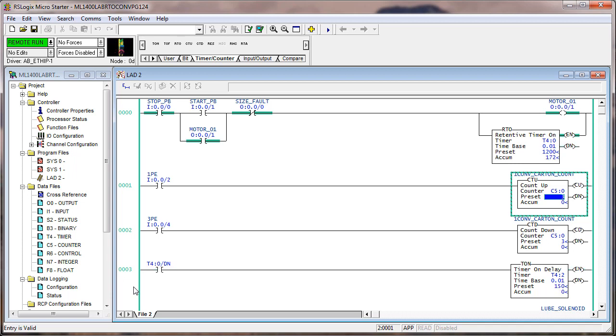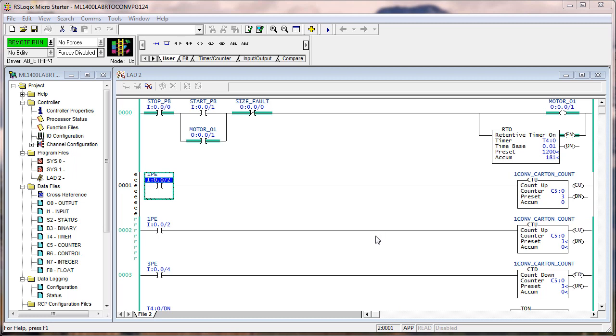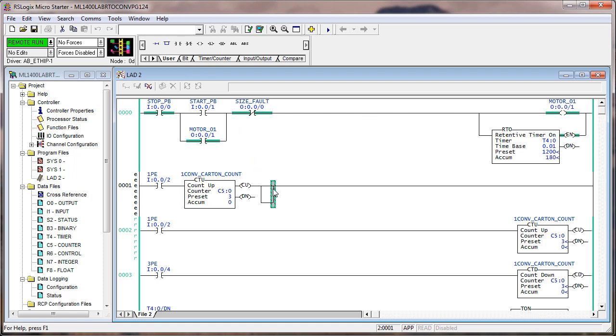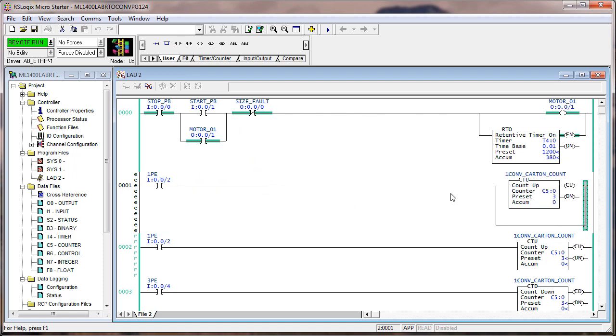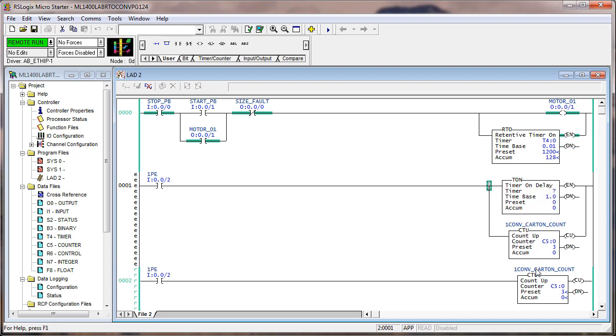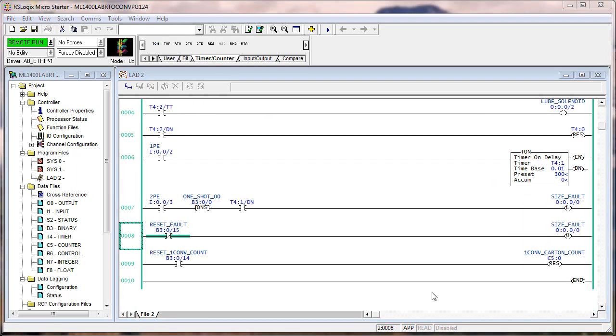You could push that button again, three PE, and it would decrement that accumulate from zero to minus one. Well there's no such thing as a minus one carton. So you can see there's a bunch of things here left to do to make this logic more complete and more plausible. I'm editing the logic to add the timers in to allow us to use the trailing edge plus a little delay to give us some singulation, put some space between the cartons. And rather than do this all without you seeing it, I want to show you an easy way to add the logic. So I put my focus on the count up instruction, then I select on the branch around. I branch it around and then I move it down. Now I can put my TON up here and so forth.